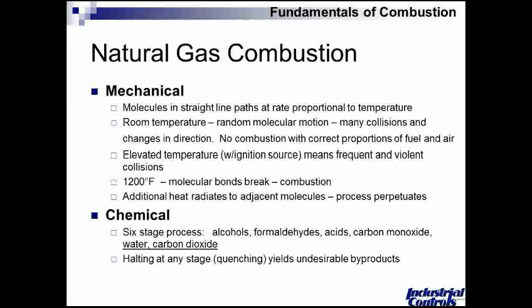If we introduce an ignition source — a hot ember, a spark, a hot surface igniter — something that can warm the fuel or mixture past that 1,200 or so degree mark (for natural gas), we'll start to affect a reaction. The bonds will break, and the beginning of combustion will occur. Even in the absence of that initial spark, the combustion reaction will perpetuate: the ignited fuel and air envelope liberates heat to the incoming fuel and air mixture, thus perpetuating the process. So while some burners must maintain a source of ignition, under most conditions that continuous ignition source is not always necessary.